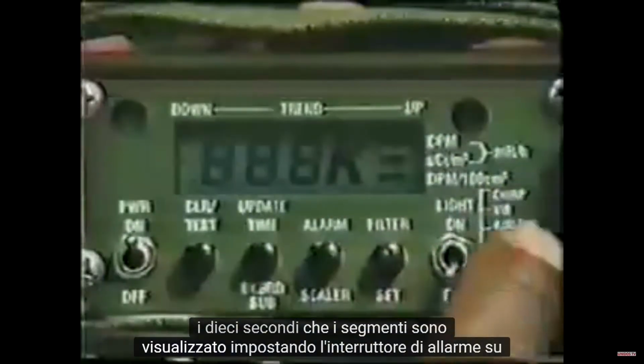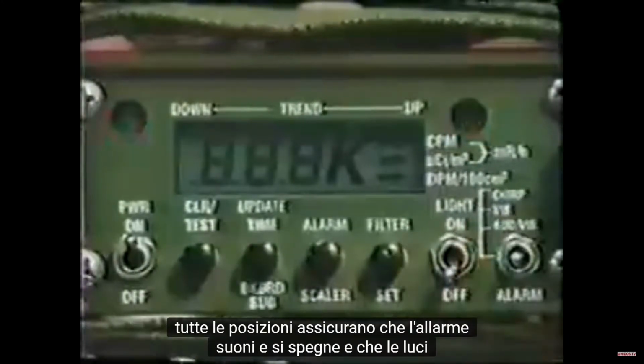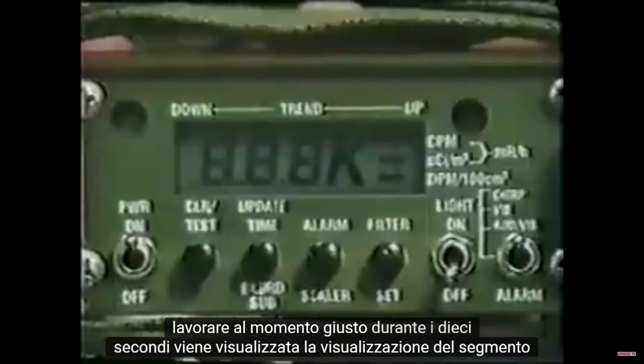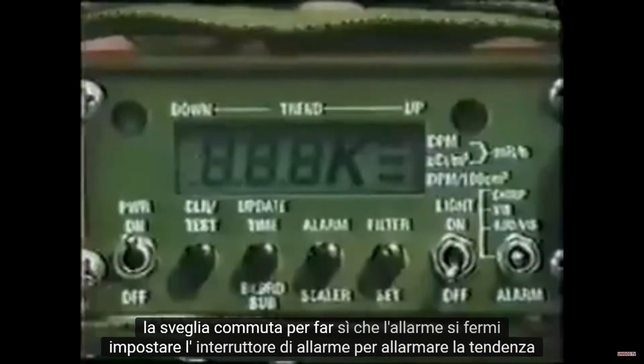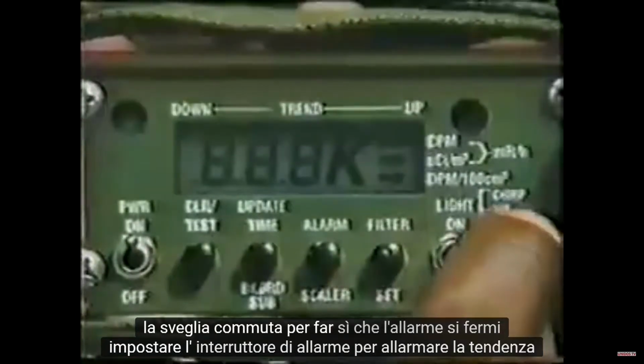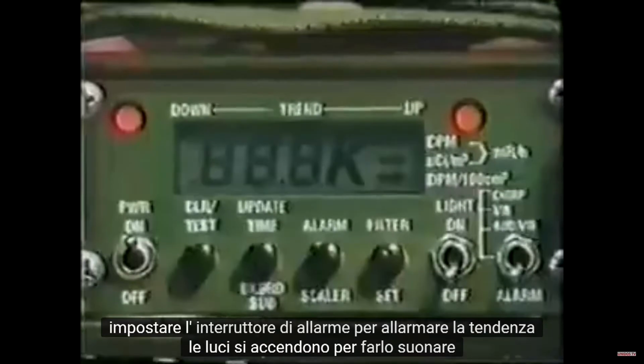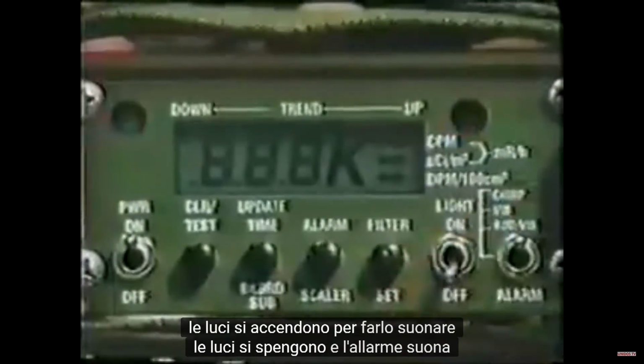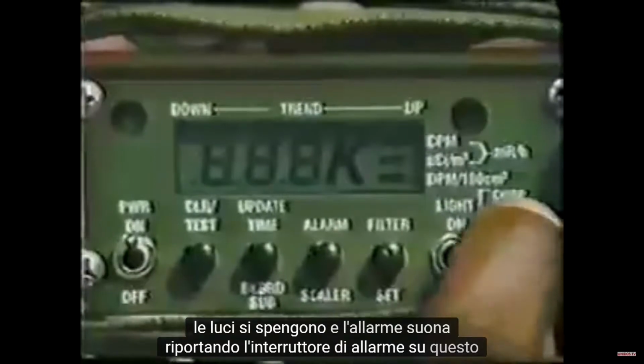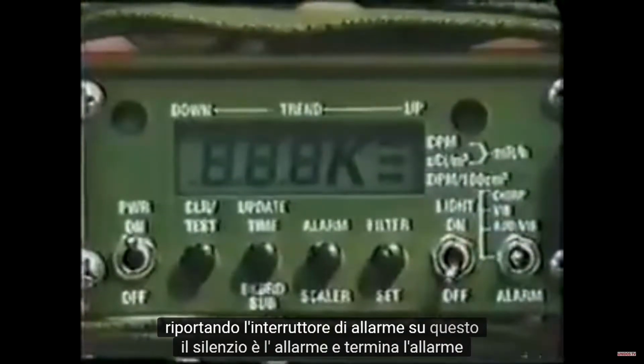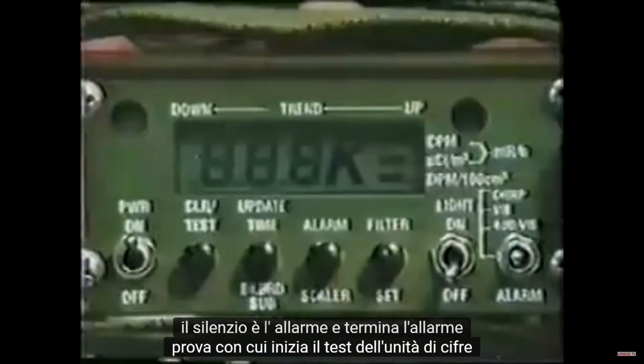The alarm test must be performed during the 10 seconds that the segments are displayed. Setting the alarm switch to all positions ensures that the alarm sounds and shuts off, and that the lights work at the proper time. During the 10 seconds the segment display appears, set the alarm switch to VIB. The alarm stops. Set the alarm switch to alarm. The trend lights come on. Set it to chirp. The lights go out and the alarm sounds. Returning the alarm switch to Viz silences the alarm and ends the alarm test.